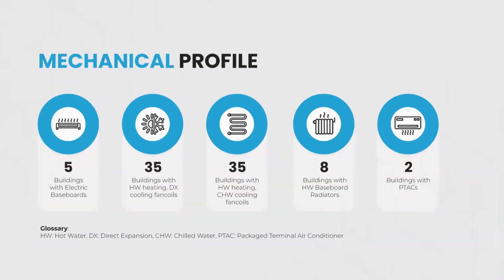In terms of mechanical systems, there's some consistency, but not ultimate consistency - these buildings vary in their baseline mechanical systems implemented over the years. They have 5 buildings that are purely electric baseboard heated. There's 35 buildings that are hot water heated but DX cooled in the suite. The way that's set up is there's a 2-pipe system delivering hot water, but all the cooling for the suites is done at each suite with a DX unit, with the condenser typically located on the balcony.